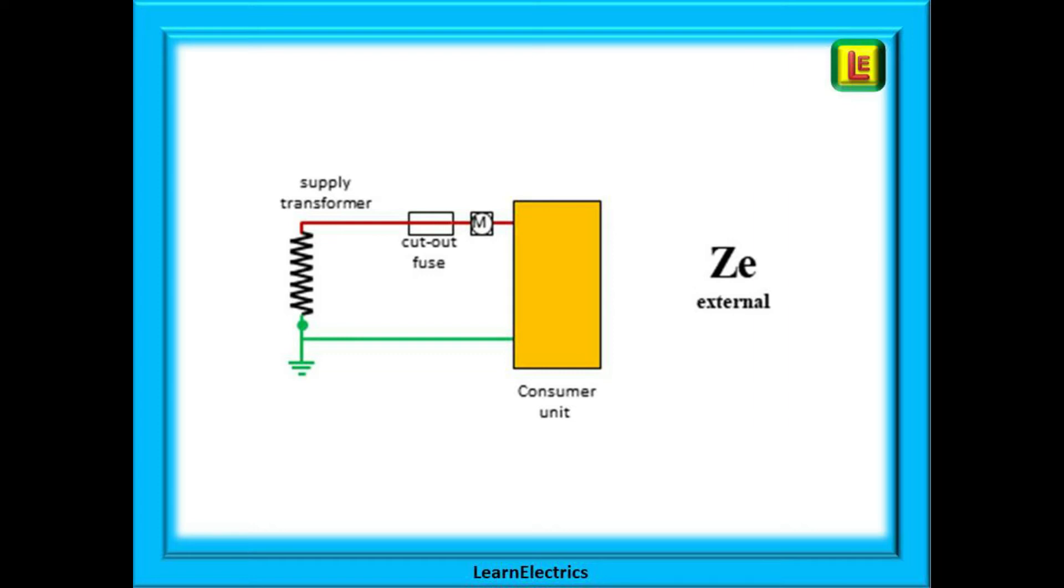Here we are showing ZE, or the external part of the electrical circuit from the consumer unit out of the building along to the supply transformer and back. Try to remember ZE with an E for external impedance. The impedance ZE is often measured at the entry point to the consumer unit and it measures the supply's equipment and cables. As we are measuring a live AC voltage outside the property, this is an impedance.